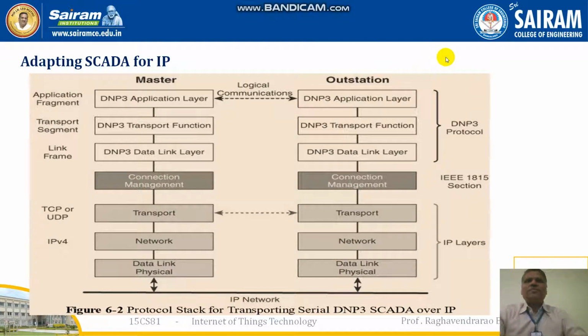Adapting SCADA for an IP. As we see on the screen, the protocol stack for transporting serial DNP3 SCADA over an IP. We can see here a 7-layer network: data link layer, network layer, transport layer, where this connection management is going to happen.